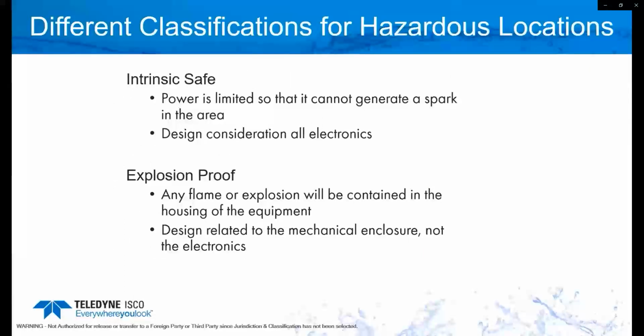Let's look at some of the different classifications for hazardous locations. Quite often we get asked, is this unit explosion proof? Is it intrinsic safe? To differentiate between the two: intrinsic safe means we're limiting the power in the electronics so there cannot be enough energy to generate a spark in that area. This is all taken into account during the design, so the electrical engineers designing products like that have to keep it in mind — that's what we do primarily with our equipment.